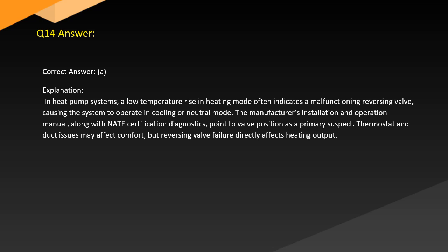Answer. Correct answer: A. Explanation. In heat pump systems, a low temperature rise in heating mode often indicates a malfunctioning reversing valve, causing the system to operate in cooling or neutral mode. The manufacturer's installation and operation manual, along with NATE certification diagnostics, point to valve position as the primary suspect. Thermostat and duct issues may affect comfort, but reversing valve failure directly affects heating output.